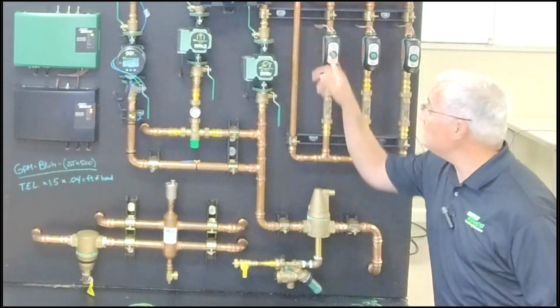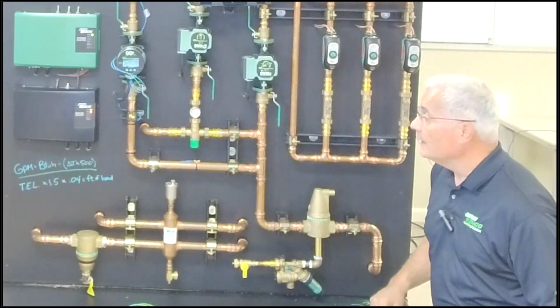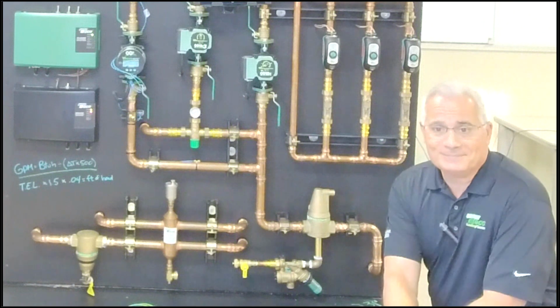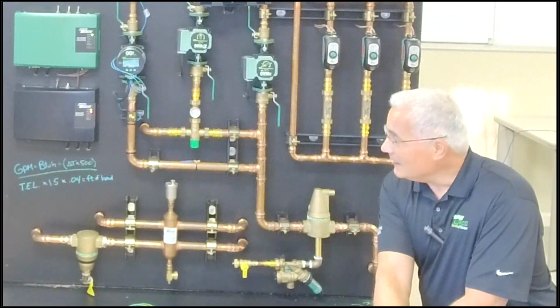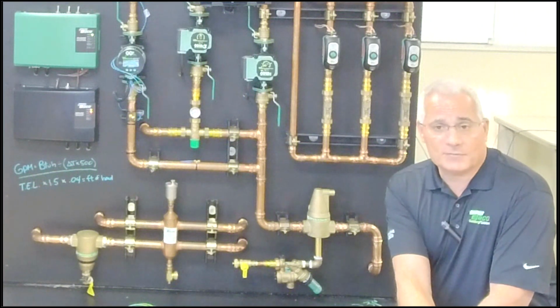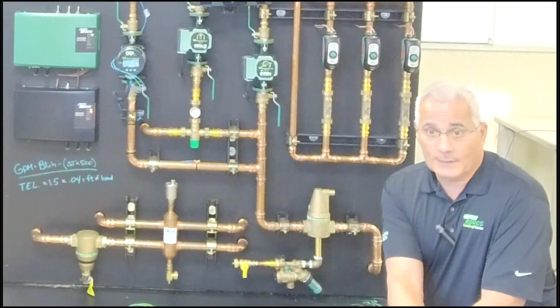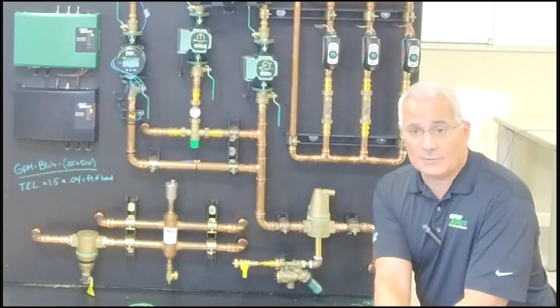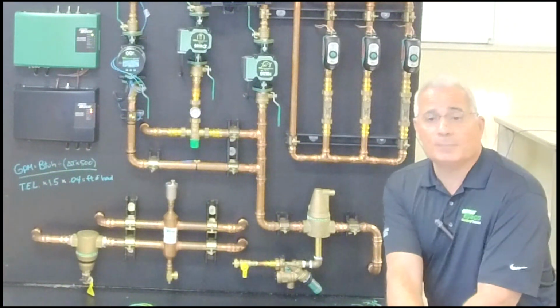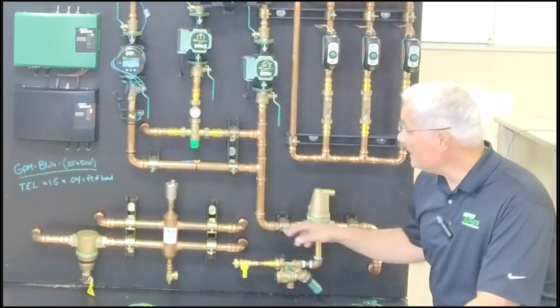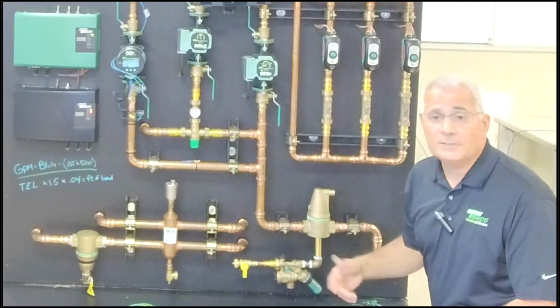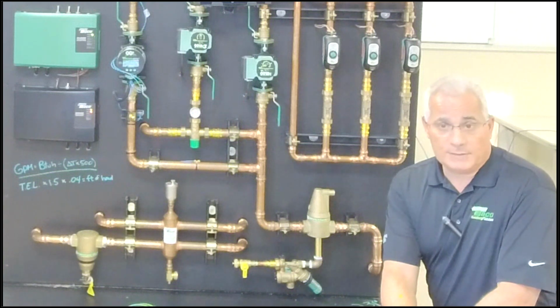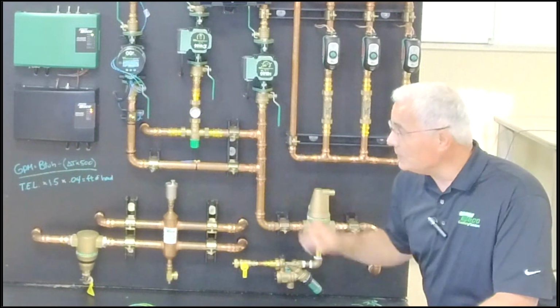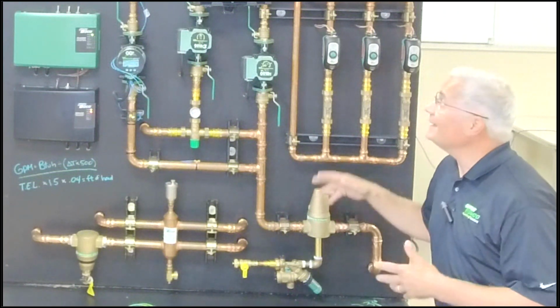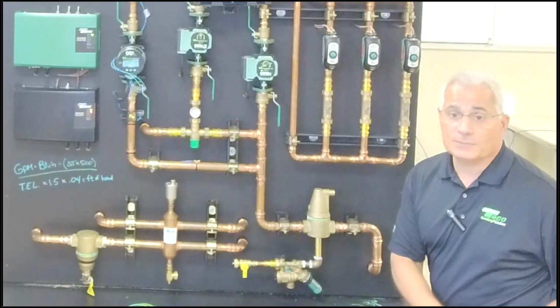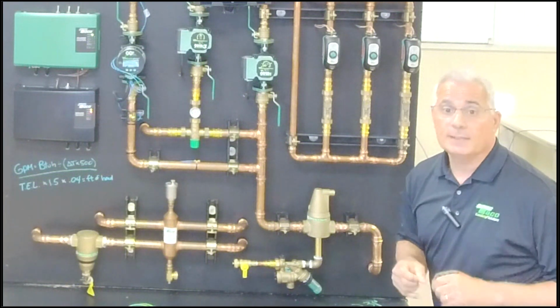So with the potential of 8 GPM going out to these 3 zones, I take my universal hydronics formula, which we have written on the board. Instead of dividing by my delta T times 500, which in this situation is going to be 20, so instead of dividing a BTU by 10,000, I'm going to take the GPM and multiply it by 10,000. Since I have the potential of 8 GPM through the piping, this should be at least up to an 80,000 BTU system. So if you recall using those formulas, looking at pipe size, I can determine the potential BTUs of this system. Without even looking at the boiler, I should have an idea of what this system can produce.